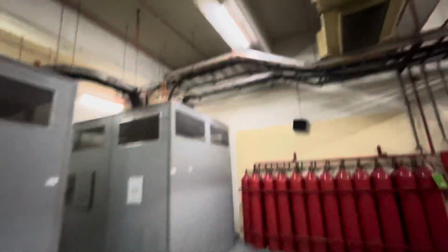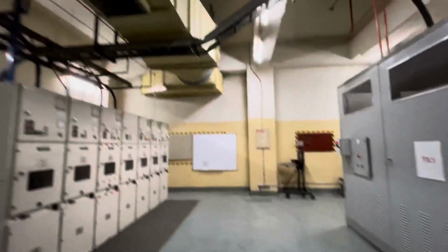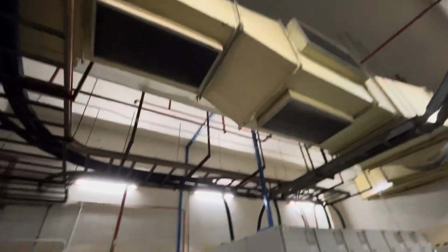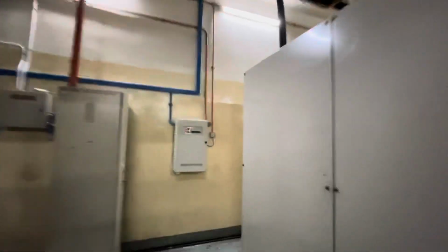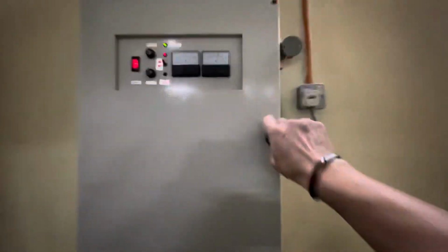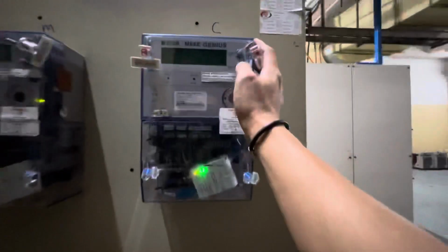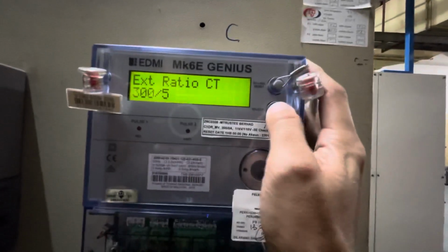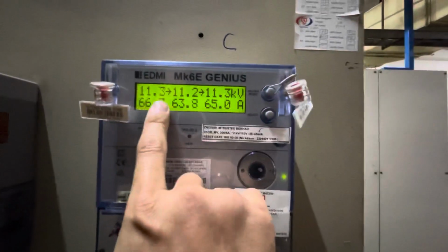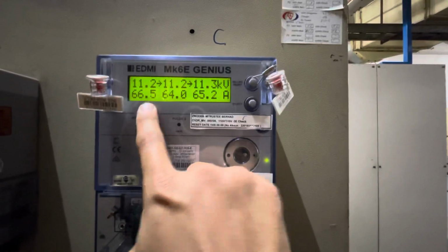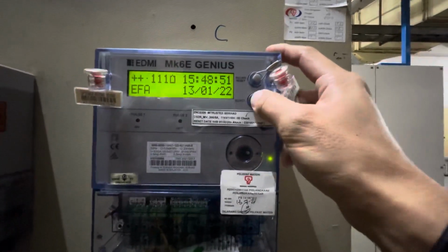Alright. Overall condition is okay. We have the rubber mat in place, firefighting system in place. The ventilation is okay. Here we have the battery. Battery is quite old. I think it's about time to replace. Alright, here we have the TNB meter. Incomer is 11.2 or 3. Currently it is using about 66 amp.